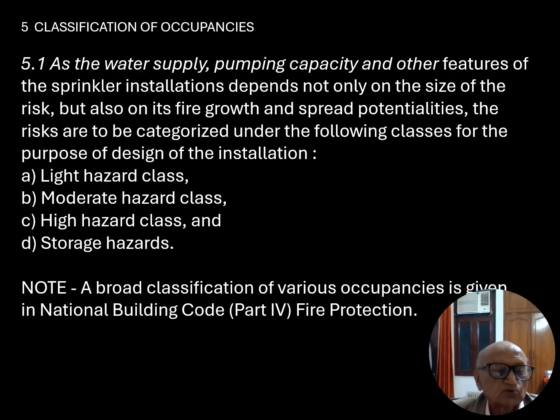Friends, I am going to present you the classification of occupancies based on hazard. As the water supply, pumping capacity and other features of the sprinkler installations depend not only on the size of the risk but also on its fire growth and spread potentialities, the risks are to be categorized under the following classes for the purpose of design of the installation. First one is light hazard class, second one is moderate hazard class, third one is high hazard class, and fourth is storage hazard. A broad classification of various occupancies is given in the National Building Code.